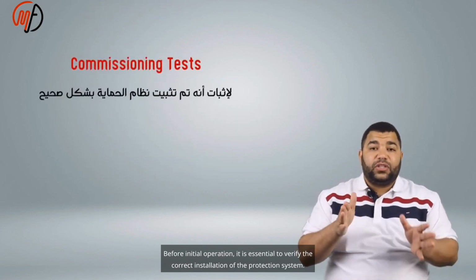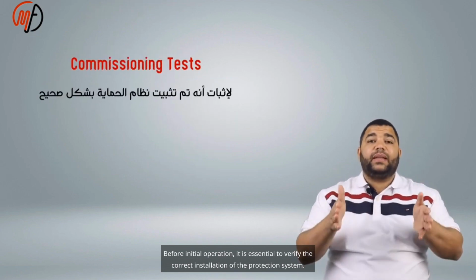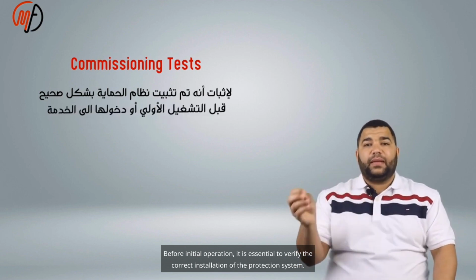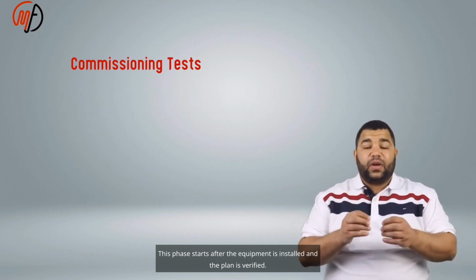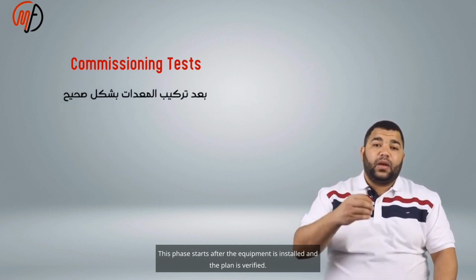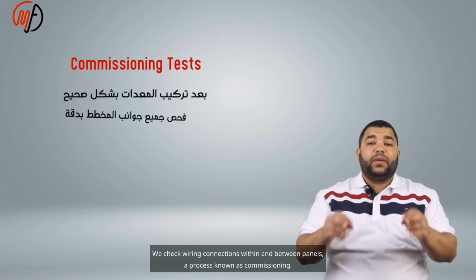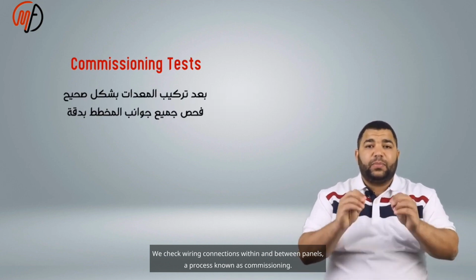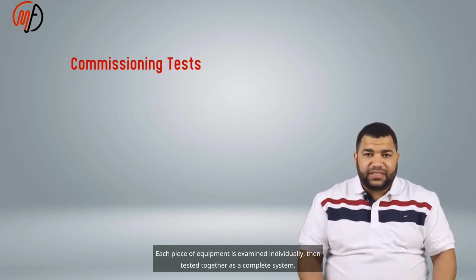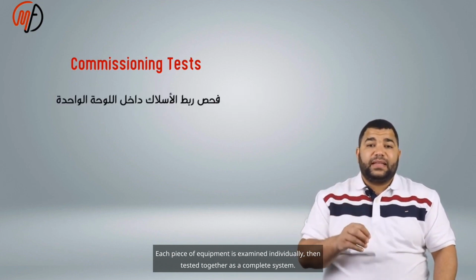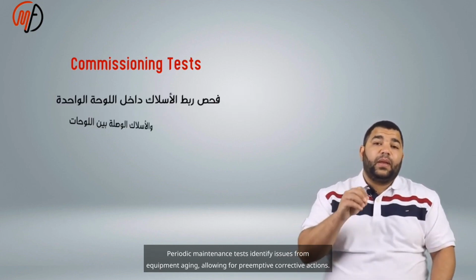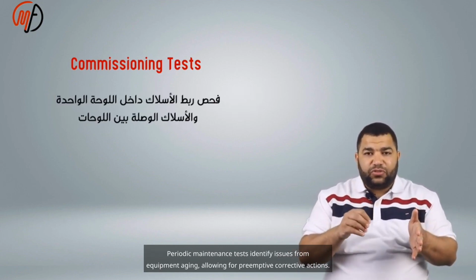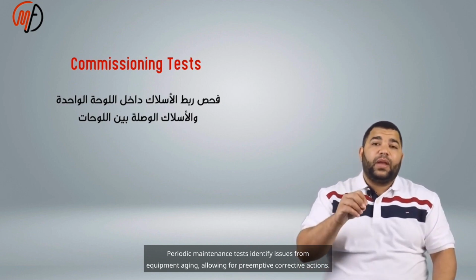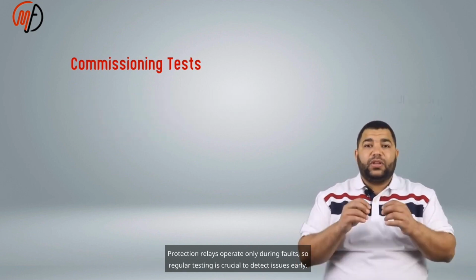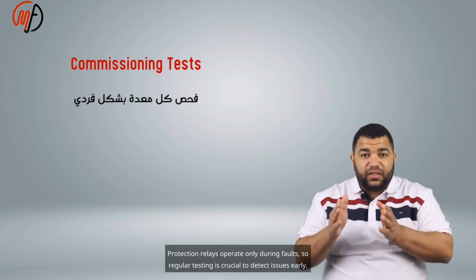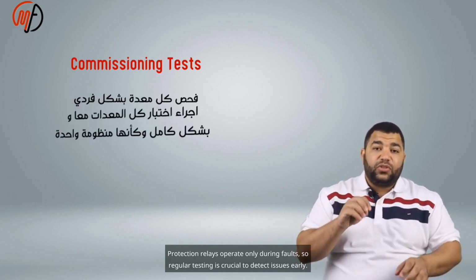Before initial operation, it is essential to verify the correct installation of the protection system. This phase starts after the equipment is installed and the plan is verified. We check wiring connections within and between panels, a process known as commissioning. Each piece of equipment is examined individually, then tested together as a complete system. Periodic maintenance tests identify issues from equipment aging, allowing for preemptive corrective actions. Protection relays operate only during faults, so regular testing is crucial to detect issues early.